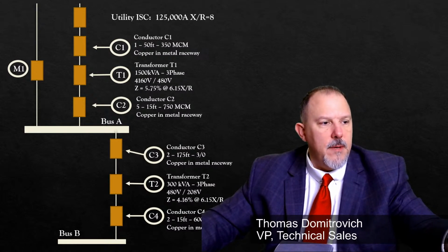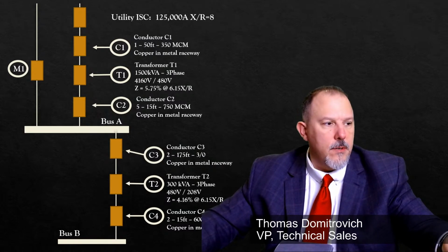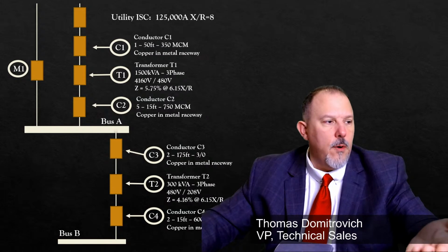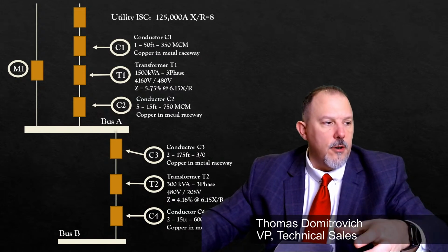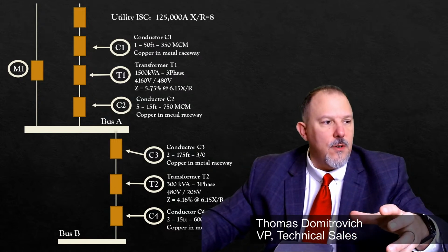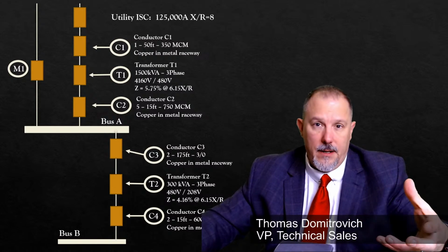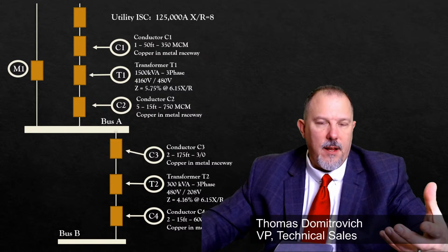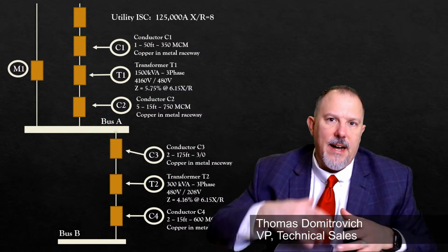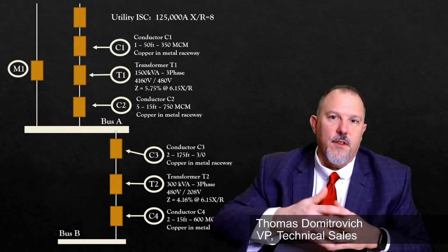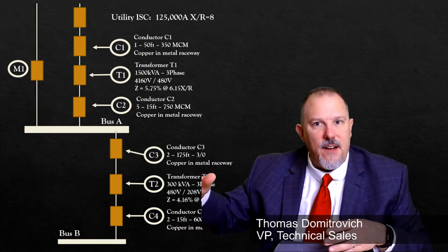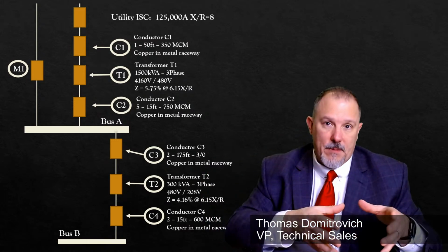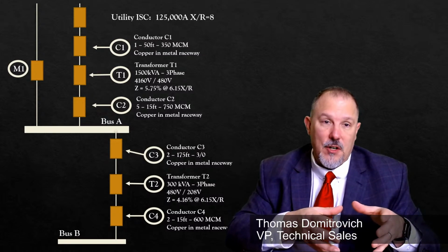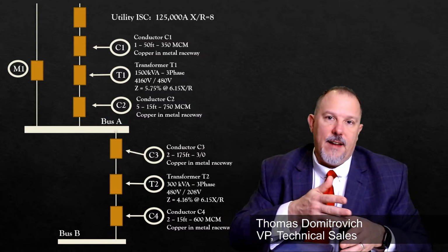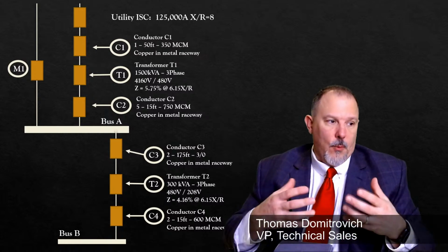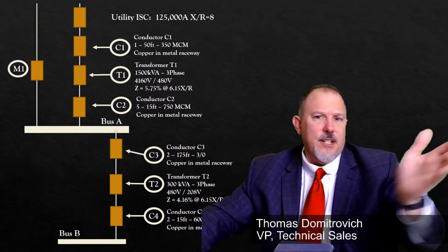So it defines 3 induction motors. It recommends omitting the group of motors each less than 50 horsepower, and applies multiplying factors 1.2 or 1.0 to the subtransient impedance of motors in the groups of larger and larger sizes. So it really depends on what you're reading. And remember, when we start modeling motors and whatnot, the motor will have a higher inrush current or a higher fault current contribution for the first half cycle. And it'll tail off, right? So what we typically worry about are the interrupting ratings of circuit breakers, the momentary duties of circuit breakers and whatnot. And so they will incorporate that for the first quarter cycle, first half cycle, so that we know what we're doing and then just forget about it afterwards.